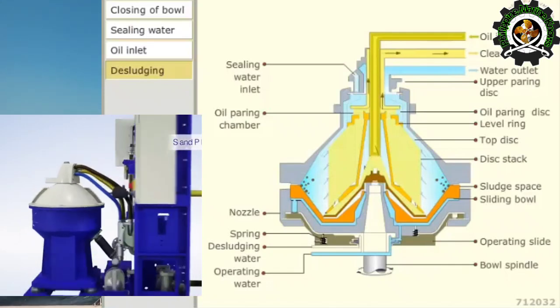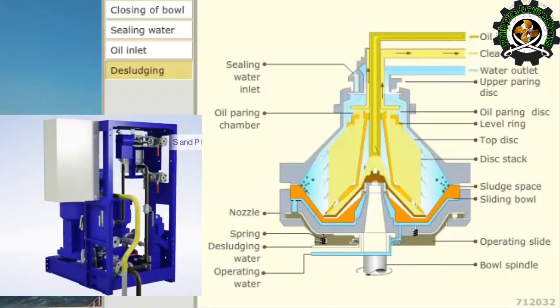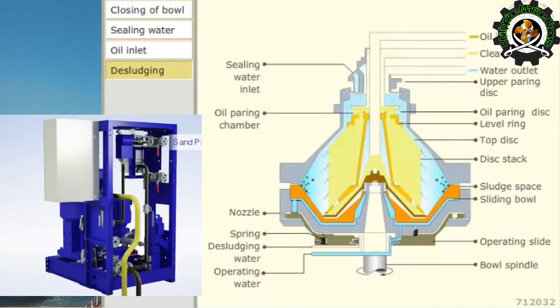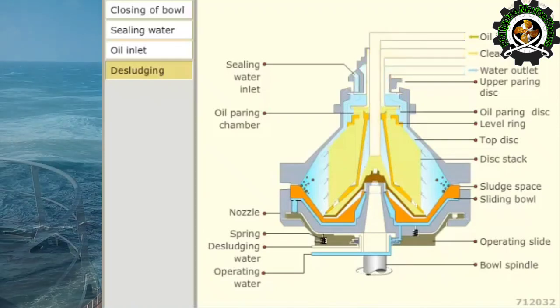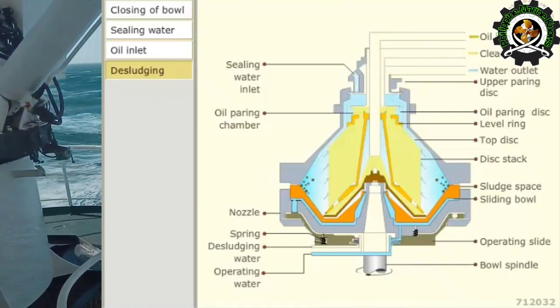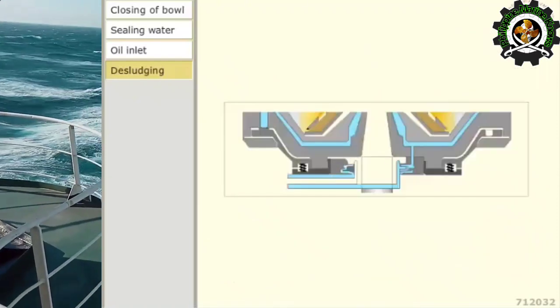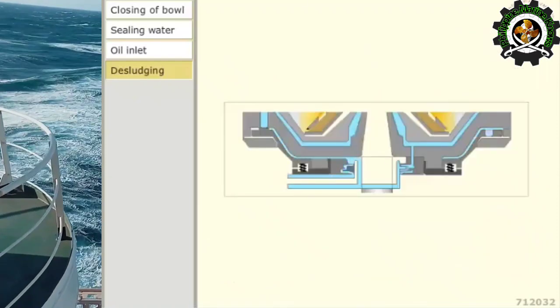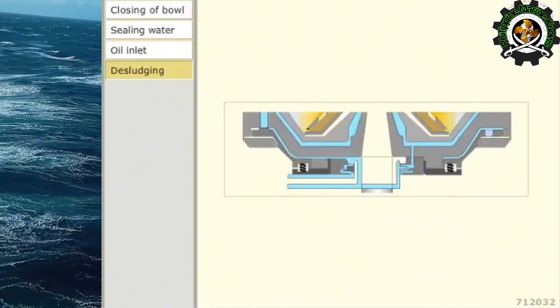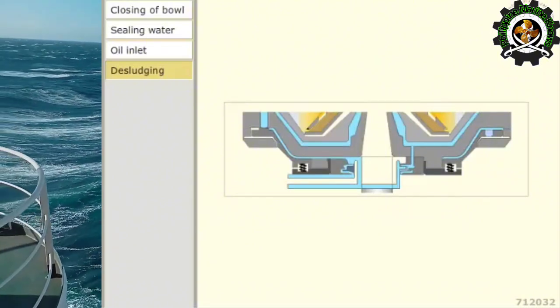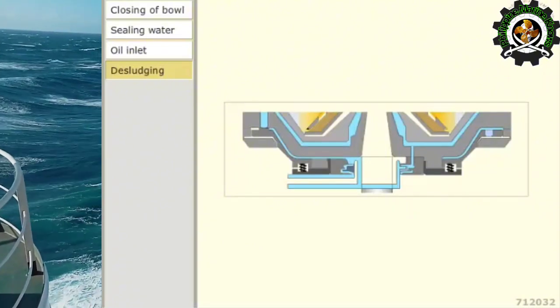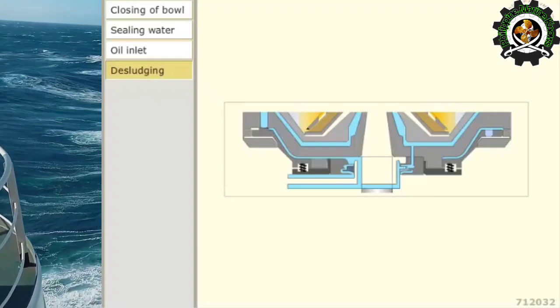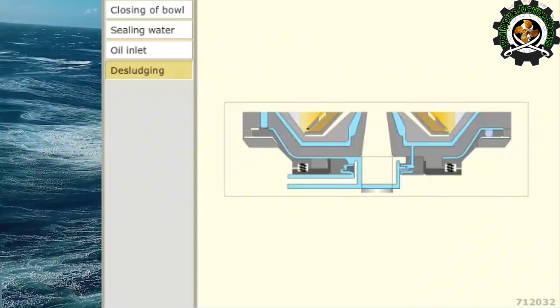For desludging, oil feed inlet to the purifier is stopped and the operating water is closed. The bowl opening water, also called the desludging water, is supplied for a few seconds during which the water flows on from the top of the operating slide.